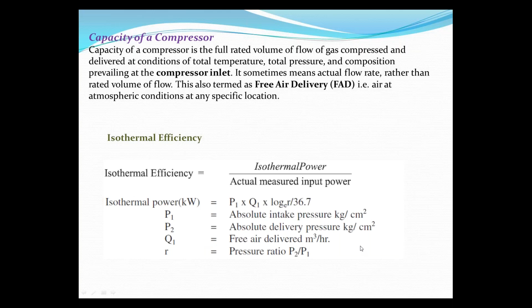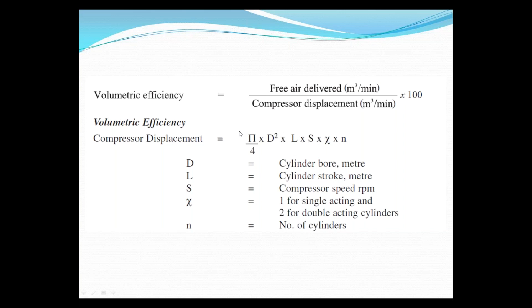So isothermal efficiency is nothing but isothermal power upon actual measured input power. Clear? And for isothermal power, I hope you remember P1, Q1, and log of the pressure ratio, log RP, and 36.7 is the multiplication factor here. P1 and P2 are the inlet and outlet pressure, and Q here is the free air delivered. Next is volumetric efficiency. We all know that it is the ratio of FAD upon compressor displacement. Compressor displacement you can calculate from the compressor specifications, meaning cylinder bore, stroke, and speed, and from this you will get the volumetric efficiency. Clear?